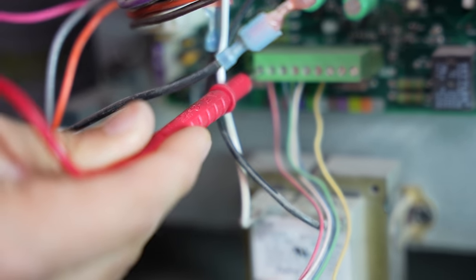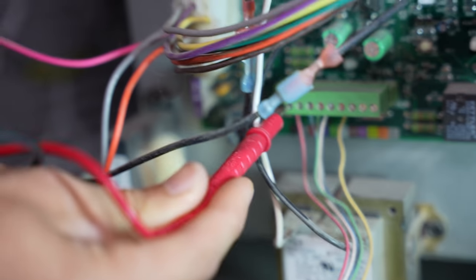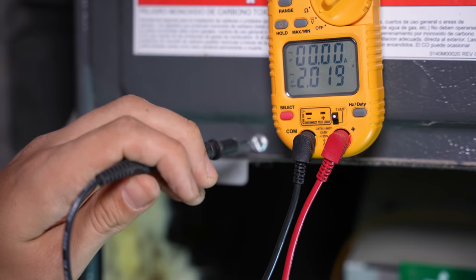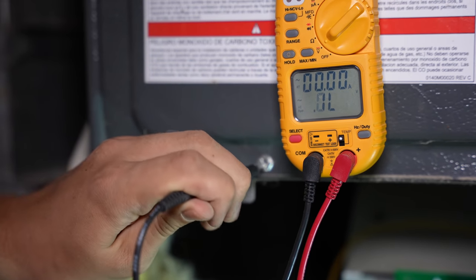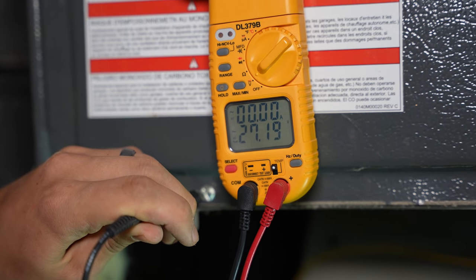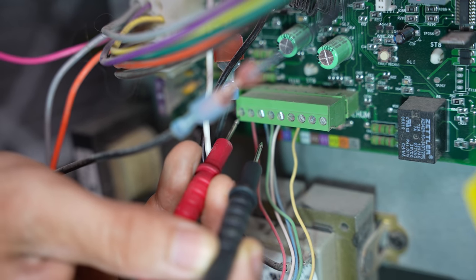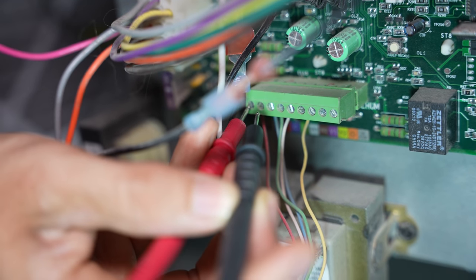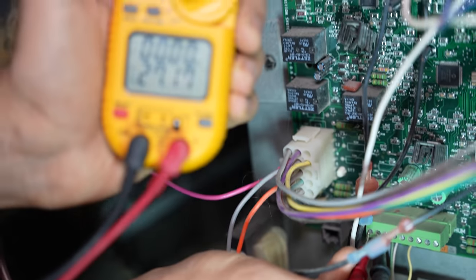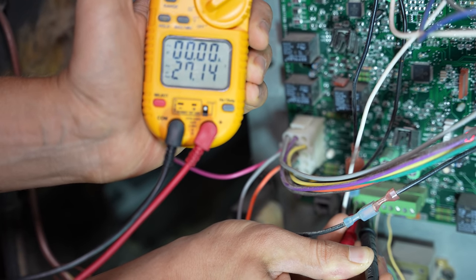Instead of the common, I can check the voltage by putting my other lead on the screw that screws into the furnace body somewhere. Just any metal screw usually will work. And as you can see, my meter is showing me 27 volts. And if I go from R to common, the 24 volt common on my meter, I am getting the same reading. And that is how you find the 24 volt common in the furnace.